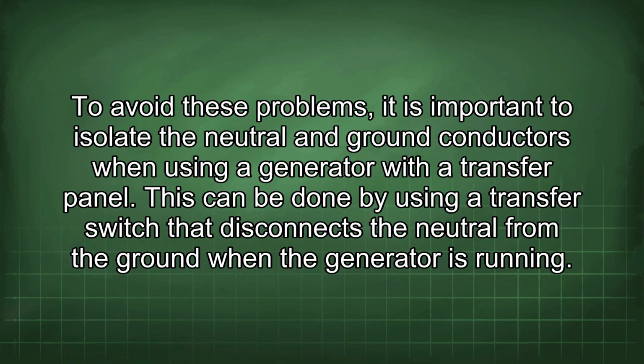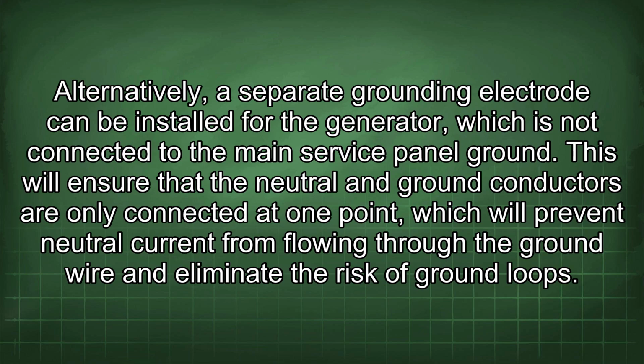To avoid these problems, it is important to isolate the neutral and ground conductors when using a generator with the transfer panel. This can be done by using a transfer switch that disconnects the neutral from the ground when the generator is running. Alternatively, a separate grounding electrode can be installed for the generator, which is not connected to the main service panel ground. This will ensure that the neutral and ground conductors are only connected at one point, which will prevent neutral current from flowing through the ground wire and eliminate the risk of ground loops.